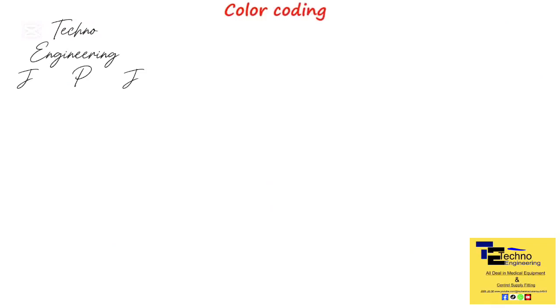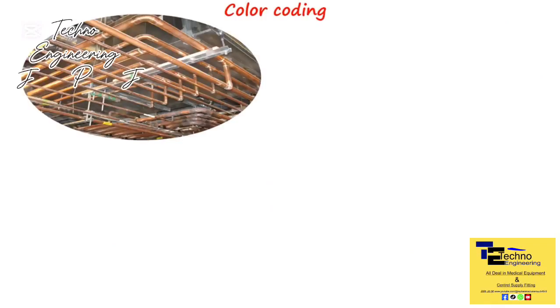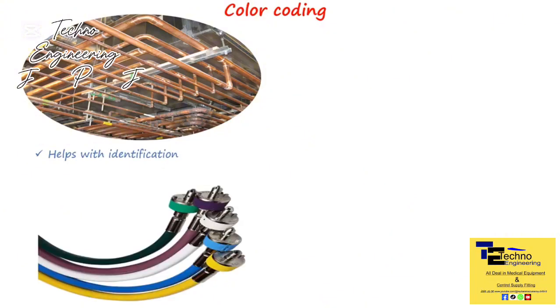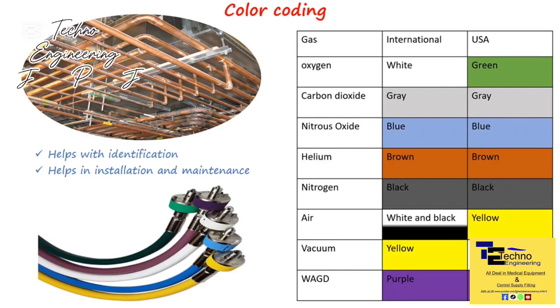The medical gas pipeline is a complex system, with a range of gases that may not be visually identifiable. Properly labeling the pipeline is crucial due to the critical nature of their usage, as using the wrong gas for a specific function can lead to fatal errors during patient treatment. Additionally, coding the pipes is essential to facilitate planning, installation, and maintenance. The color coding system adheres to cylinder codes.